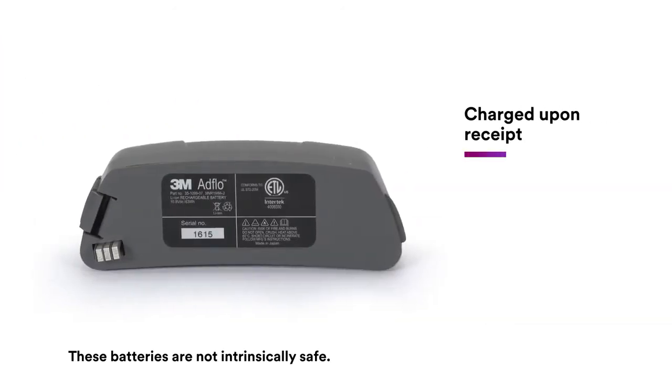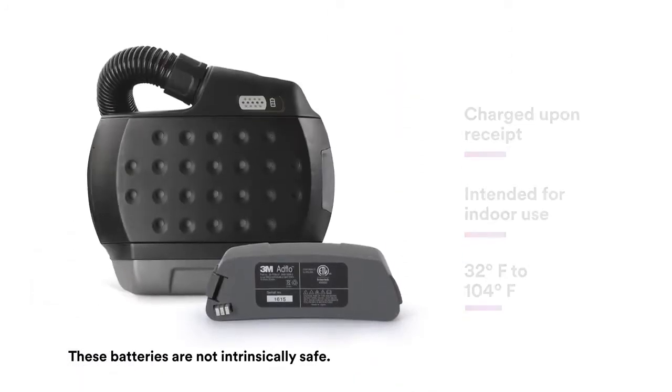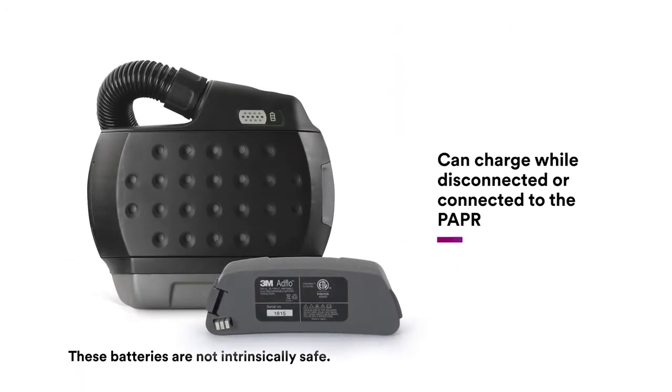New battery packs should be charged upon receipt. The chargers are intended for indoor use where they are protected from moisture. The charging temperatures are from 32 degrees to 104 degrees Fahrenheit. The battery pack can be charged separately or attached to the 3M AdFlo PAPR assembly.